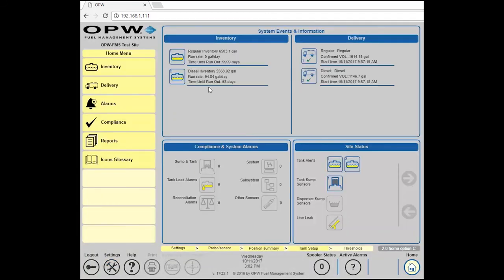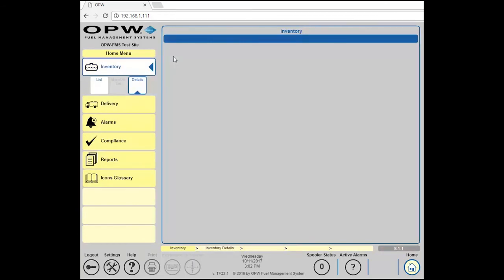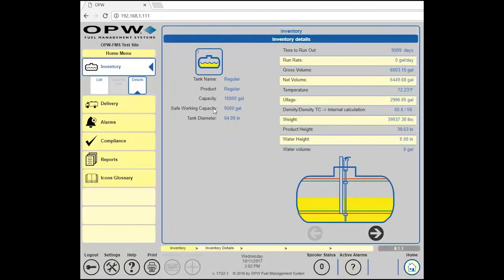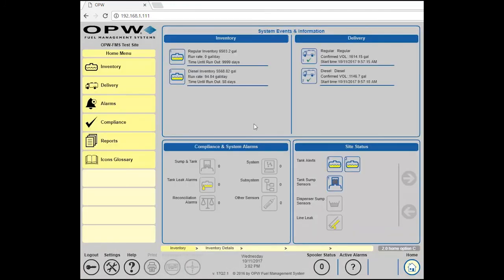And we come back out to our screen. Select that tank, and you notice that we no longer show our water height or our water volume in the inventory screen, because we are now actually reading the density of the product at the bottom of the tank. That's all there is to it. It would normally take maybe 30 minutes per tank to get one installed, set up, and correctly programmed.